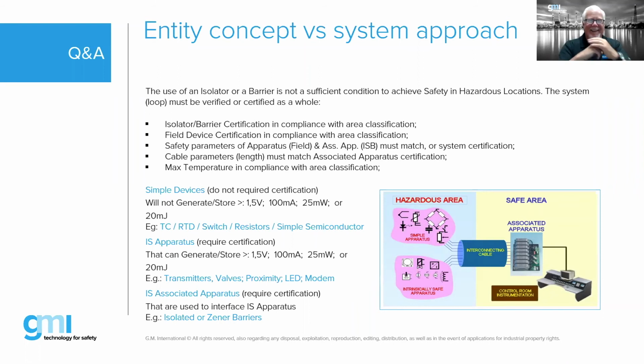Okay. So basically, the entity concept is more or less taking the details of all of the devices in our system, if you will. For example, if we take a transmitter or an intrinsically safe associated apparatus, a barrier, we're taking into account all of the output parameters and input parameters, all of that information for those individual devices, and we're looking at them as a system. So we basically have to go through these types of checklists that you see on this slide. Is the barrier in compliance with the area classification? Cable parameters must match. Then we take a look at our simple devices, and simple devices, by the way, do not require certification.